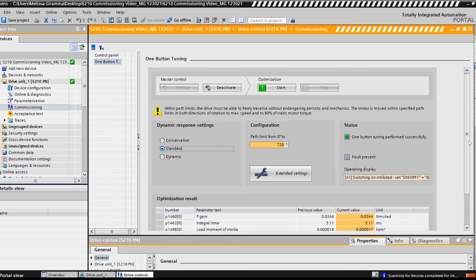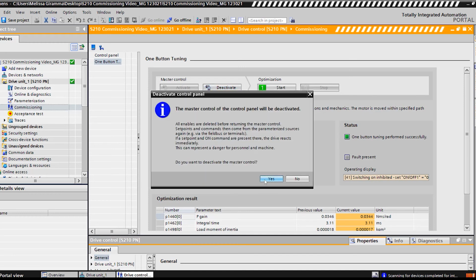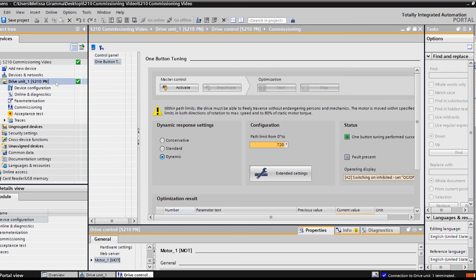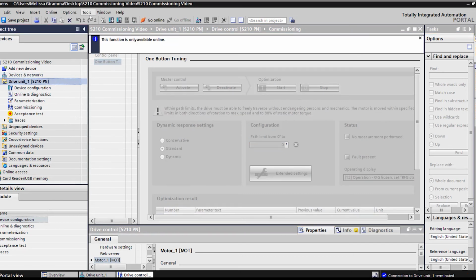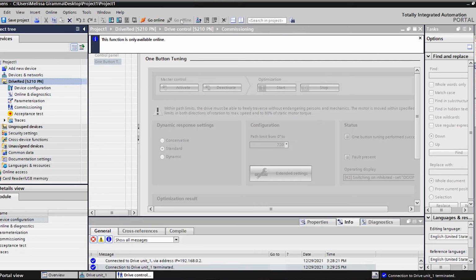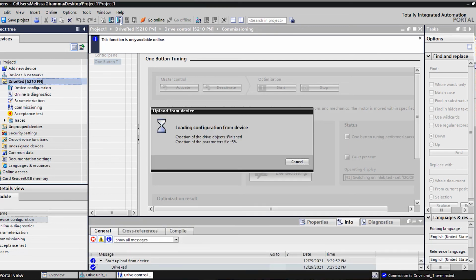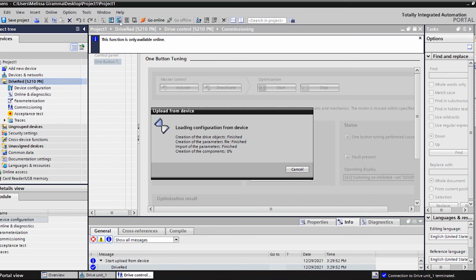When the tune is complete, deactivate the control panel. And then go offline with the drive. The tune was completed online, so we want to perform an upload from device to make sure that the parameters we set on the S210 are the same as in our project. This completes the 2 minimum commissioning requirements, and we can save the project.